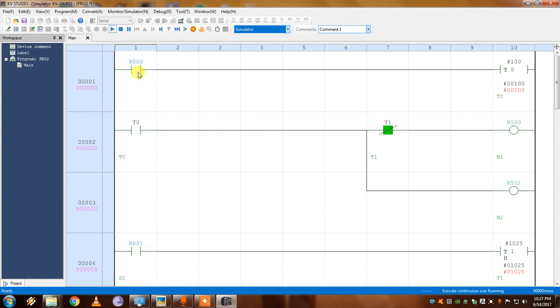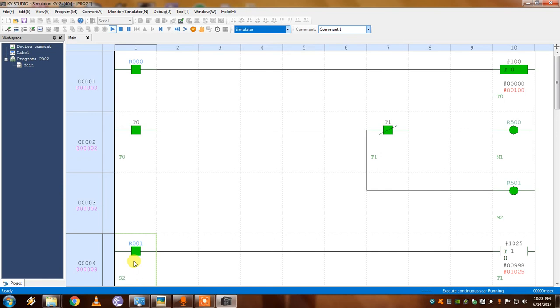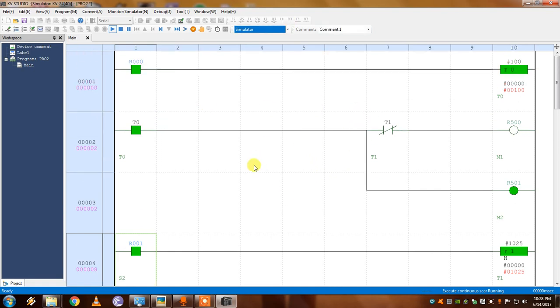Let's check it in simulation mode. The play button is given. If S1 is on, after 10 seconds M1 and M2 will be on. If S2 is on, after 10.25 seconds M1 will be cut off. M1 is cut off. The high-speed timer TMH is used when high accuracy is needed. This is how the timer works.